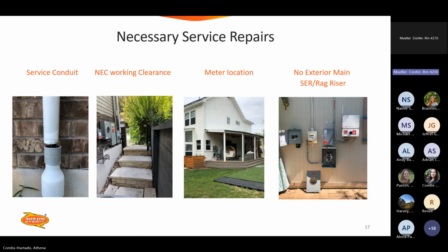That second picture, the working clearances in front of that service equipment there, you've got steps, which are less than 30 inches wide. So right, the rule is 30 inches wide or as wide as the equipment, 36 inches deep and 6.5 feet tall. So if you've got a staircase, something's got to be done right there in order to have those working clearances.